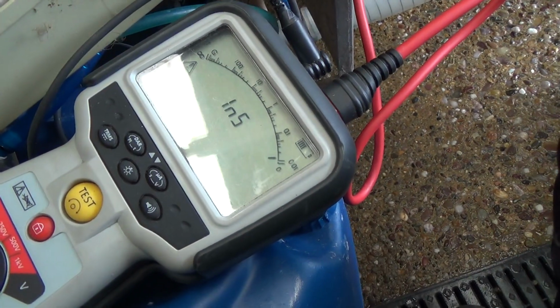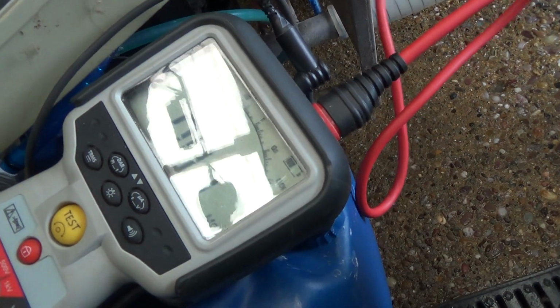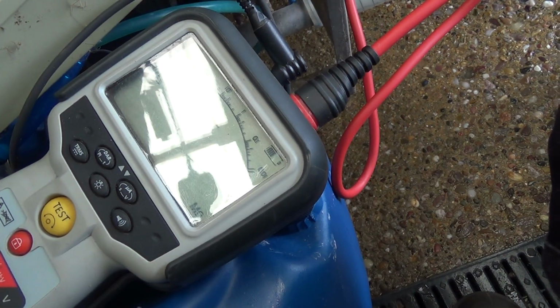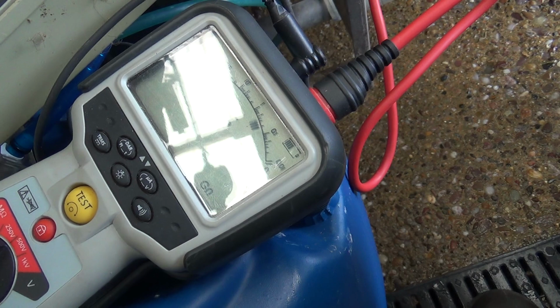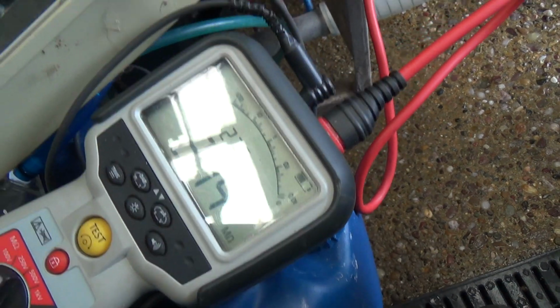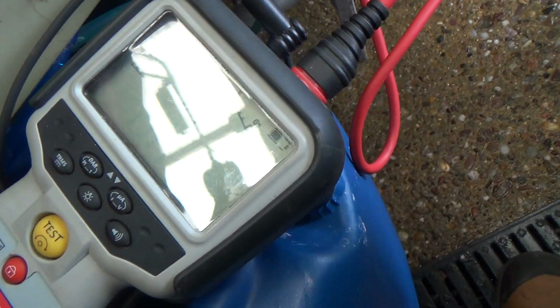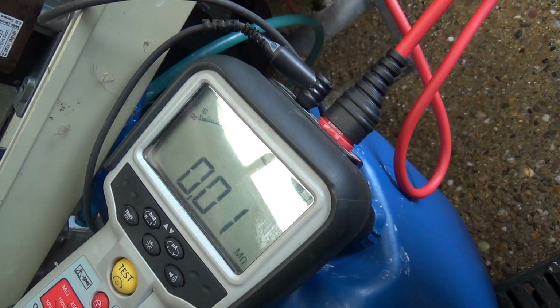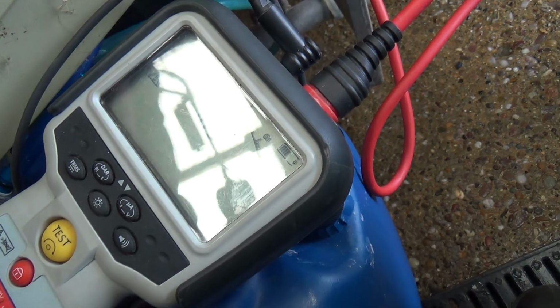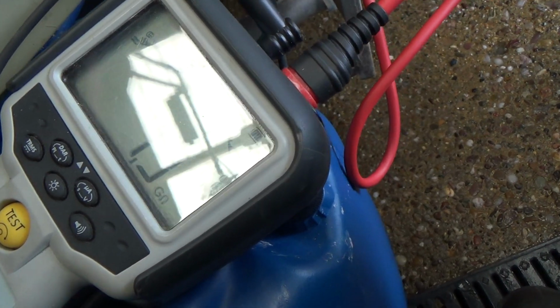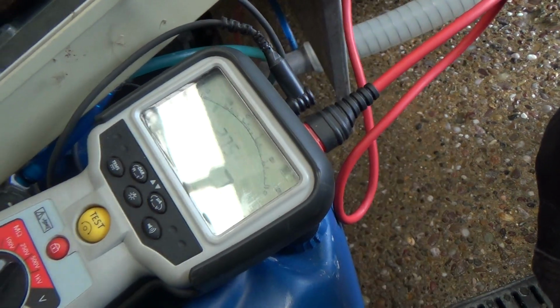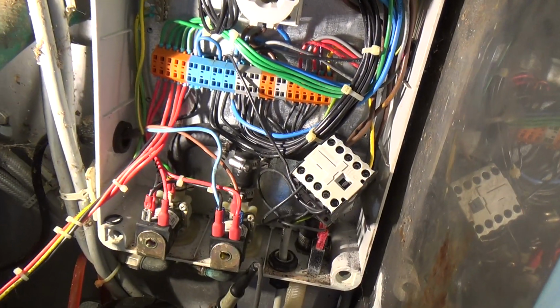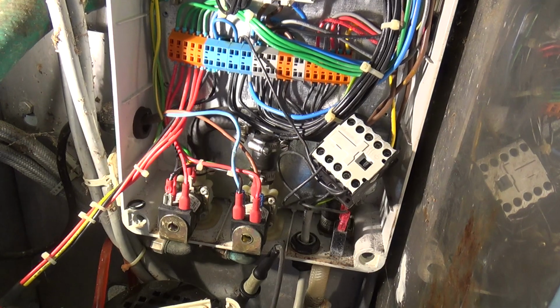Okay, that's the incoming. Oh, that's one of the lives coming in. That's a short. That's the other live. And that, I think, is the neutral, which I'd expect to also be short. Why is that one shorted? Is that one shorted? That one, if we've got a good connection, is off the scale. And that one is the neutral, which you would expect to be shorted also, wouldn't you? Because obviously, something's shorted on the live, you'd expect it to be shorted on the neutral.